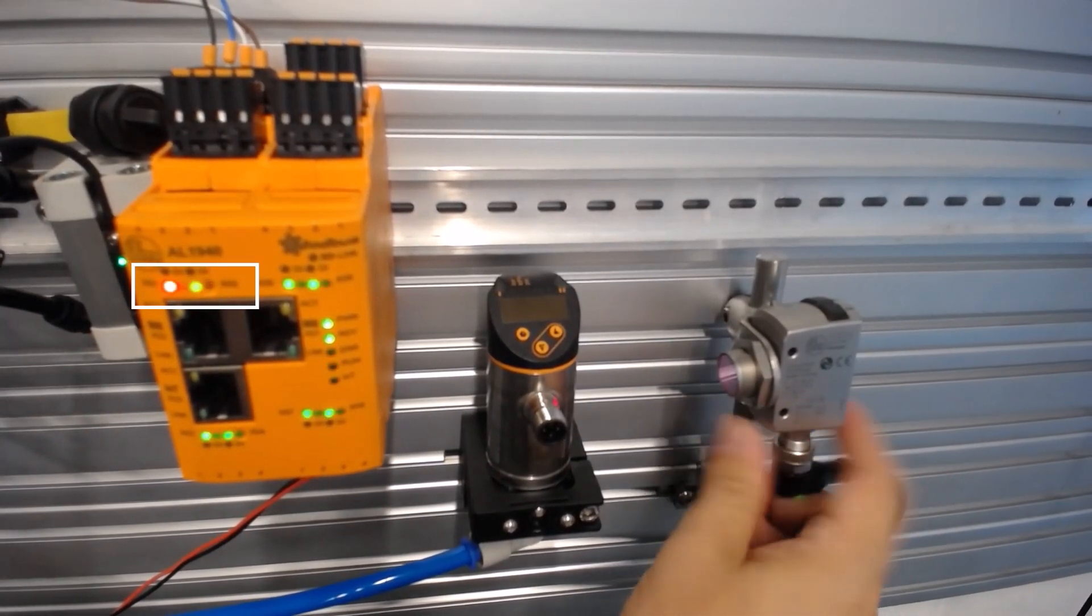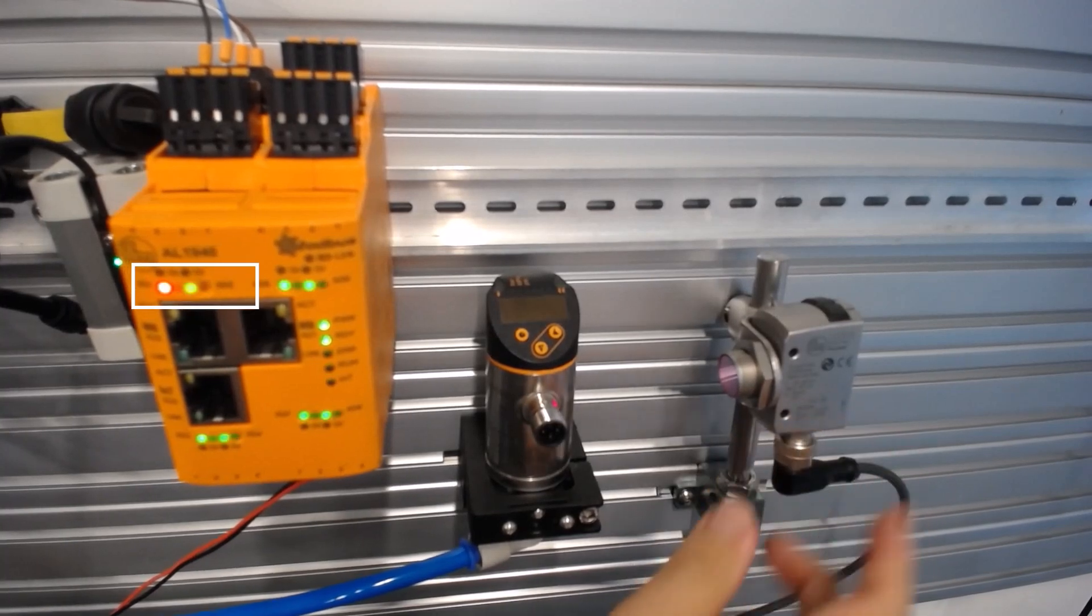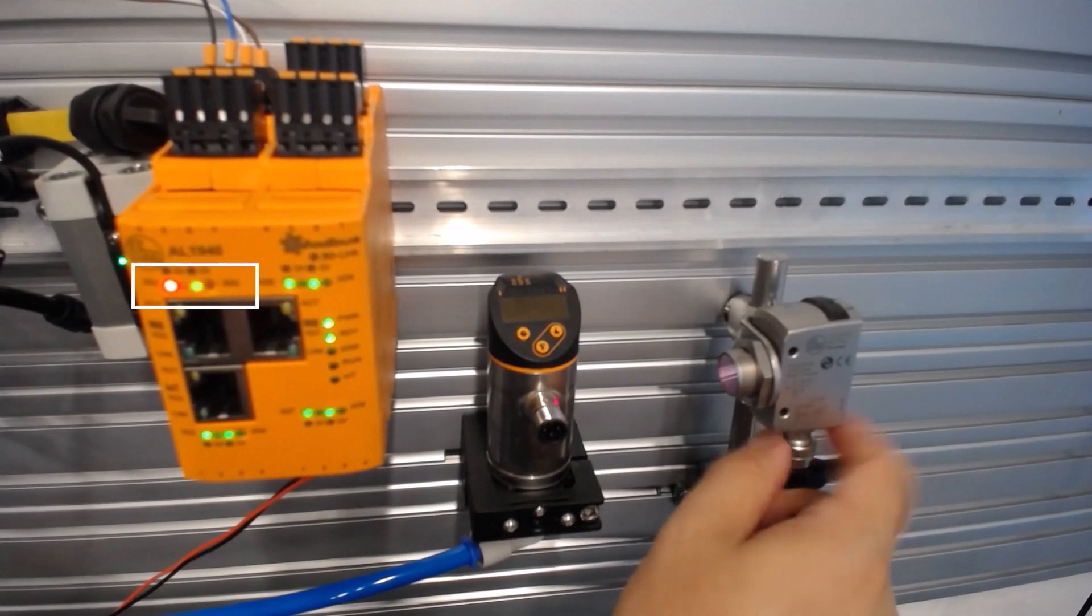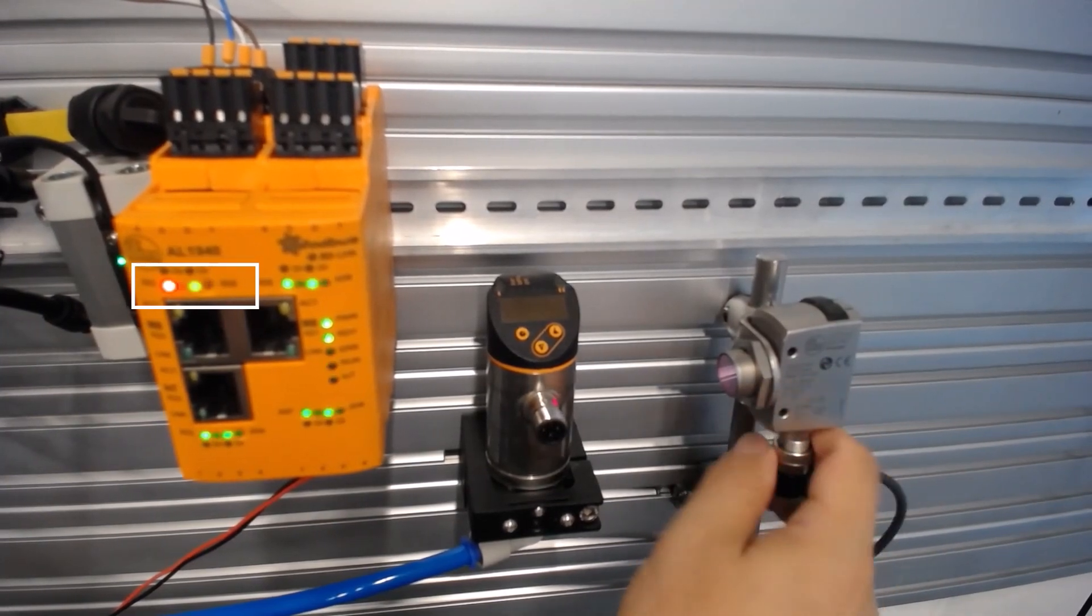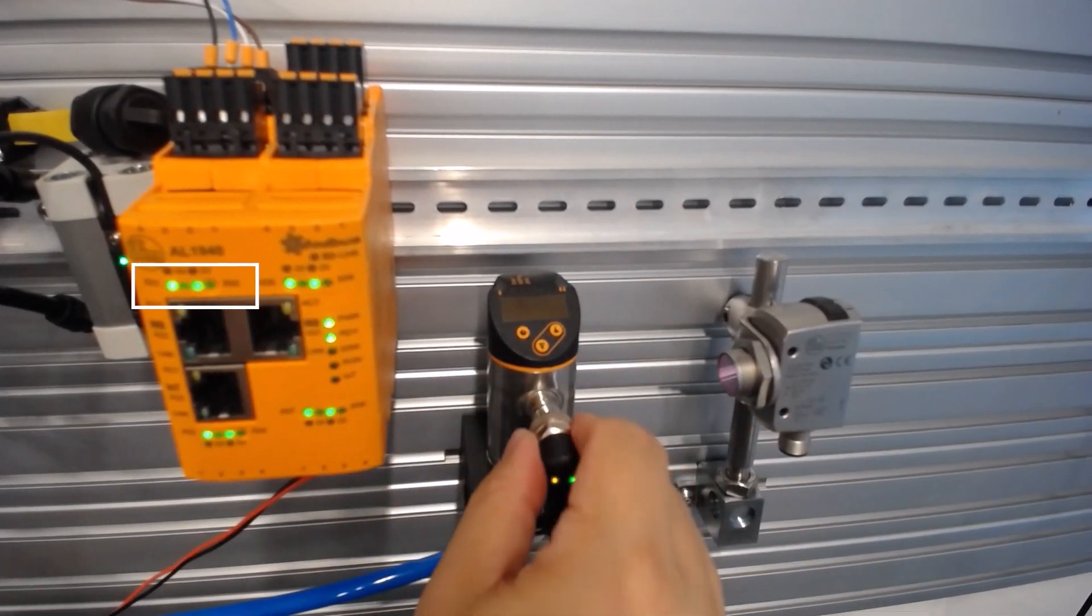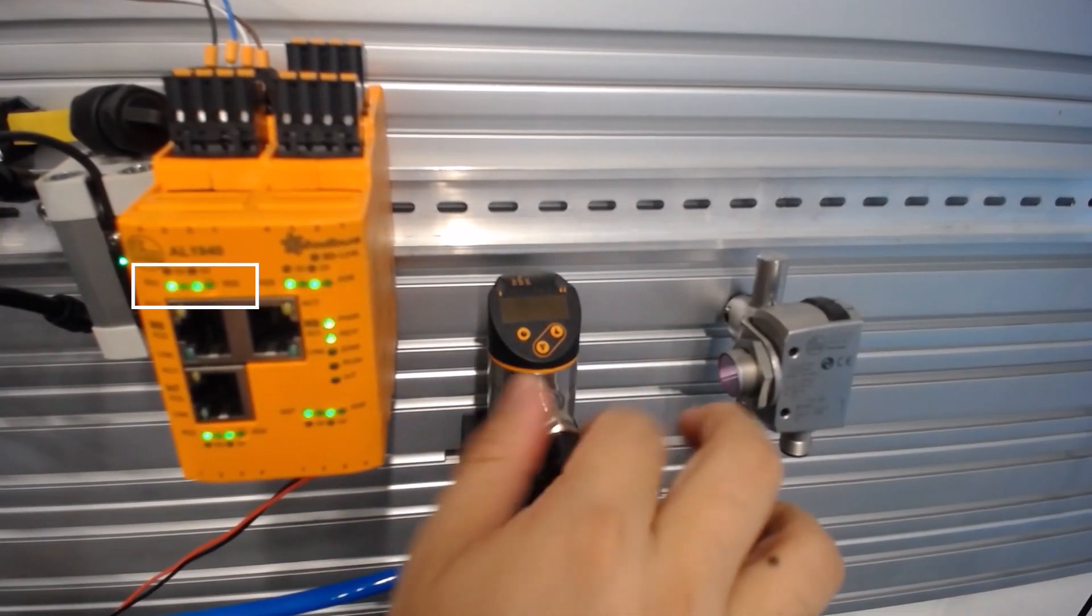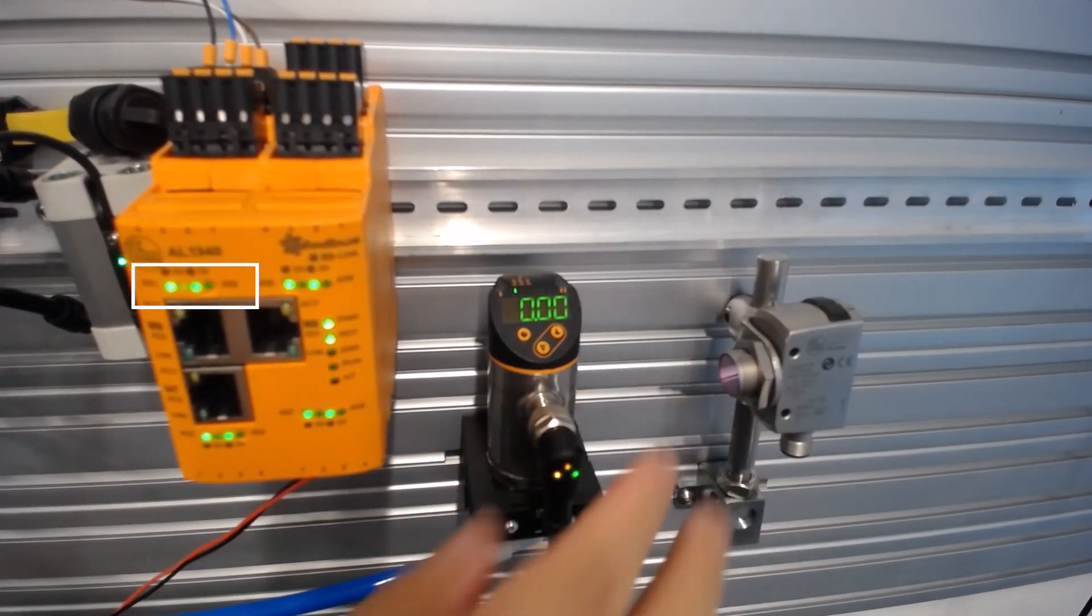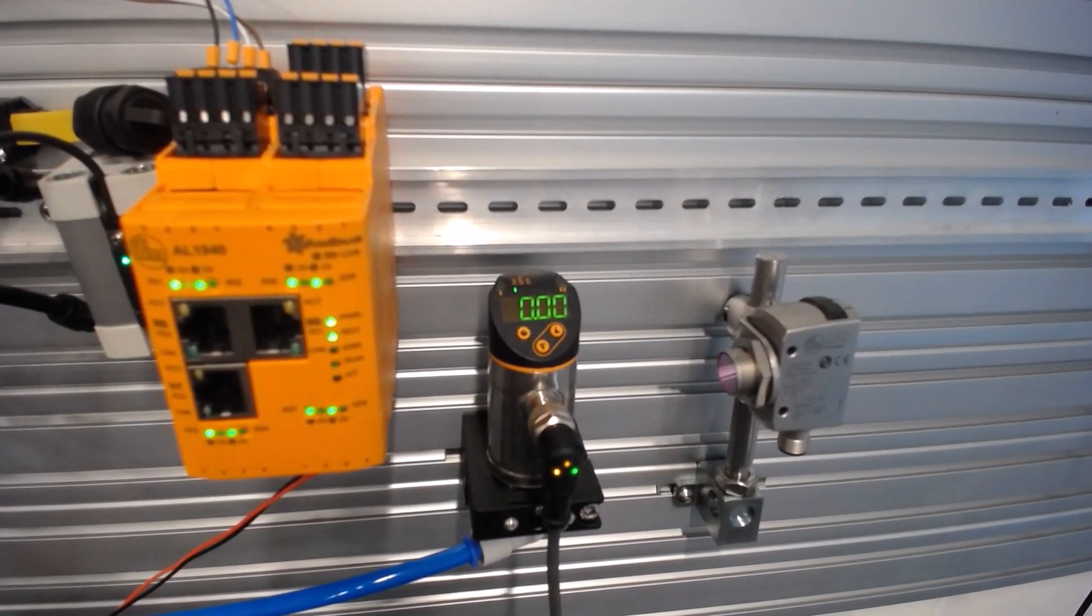Now we unplug the M12 connector and plug in another sensor. If an incorrect device with a different vendor or device ID is used, this will be recognized by the master. The process values will not be read out and the status LED will change to red. Only when we reconnect the correct pressure sensor does the LED color of port number 1 change back to green. The master accepts the wired sensor and reads out the process values.